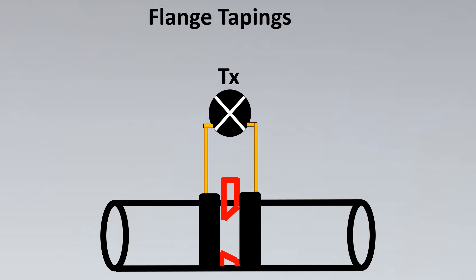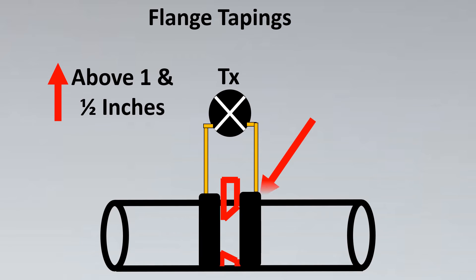Now let us look into the next case which is flange tappings. For flange tappings usually we go for line sizes which are above 1.5 inches. Now here this standard for using these flanges is ASME B16.36.